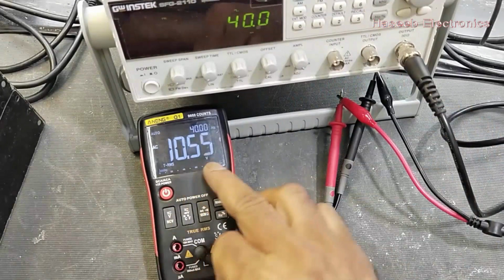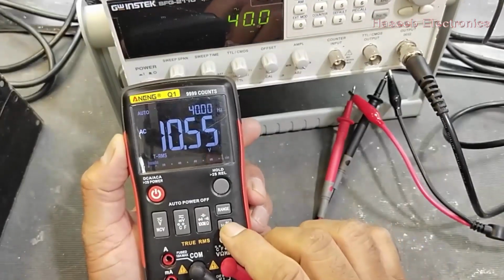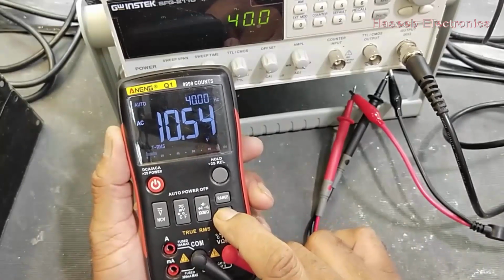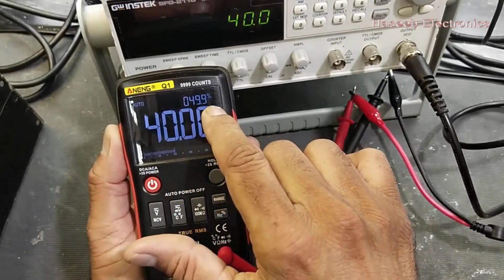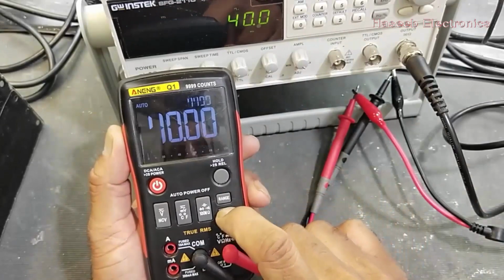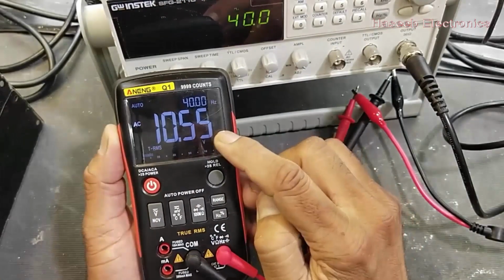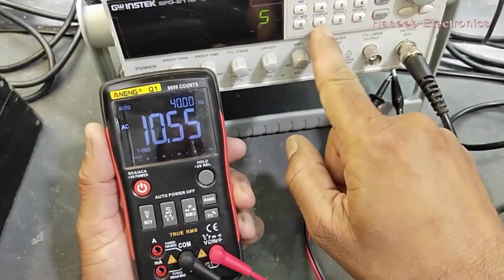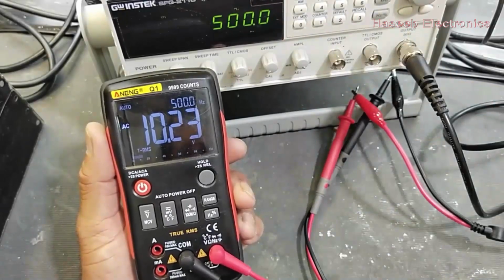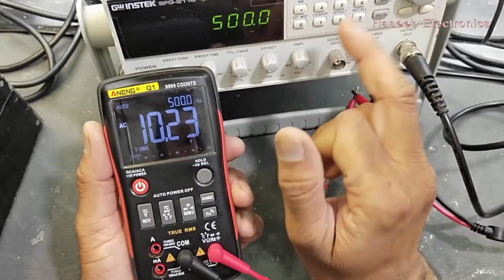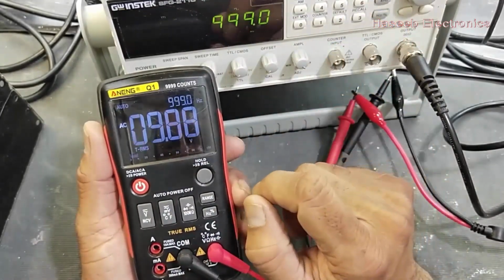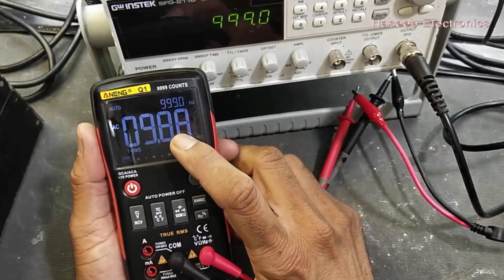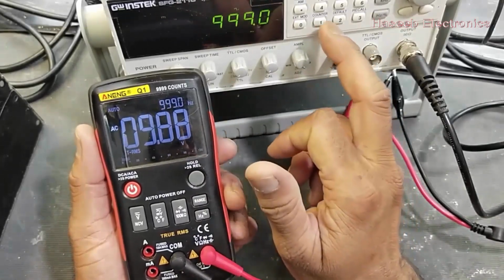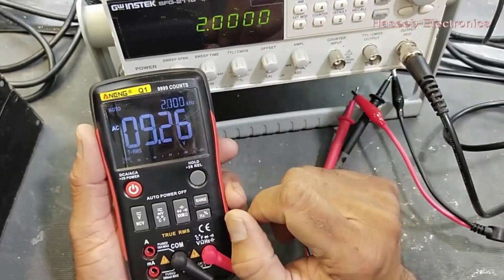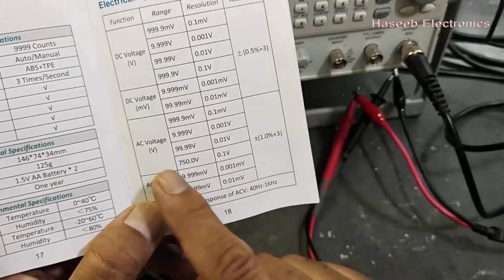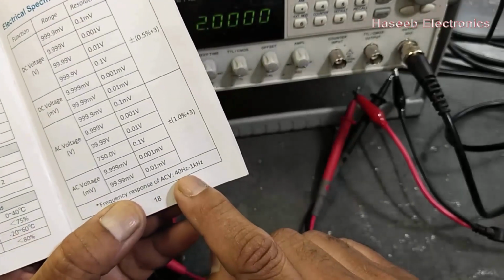Hz. I have 10.5 volt, and if you want to check the duty cycle of this frequency, just press this frequency button. So 40 Hz, 49.9%. This is duty cycle. Press this button again and we will go back to the same menu. It is 10.55 volts. Now if I press 500 Hz, it is giving 500 Hz, 10.23 volts. If I press 999 Hz, the voltage level dropped to 9.88, and if I put frequency 2 kHz, the voltage started dropping. This is AC voltage frequency response, ACV, 40 Hz to 1 kHz.